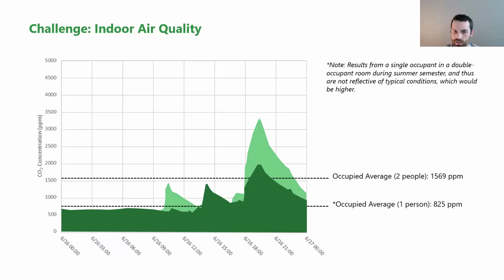Our strategy: we know we need to increase our ventilation rates, but we have an energy limitation since we're trying to reduce energy, and bringing in more outside air through those unit ventilators would increase it. So we decided to provide a dedicated outside air system, which would give us two benefits.